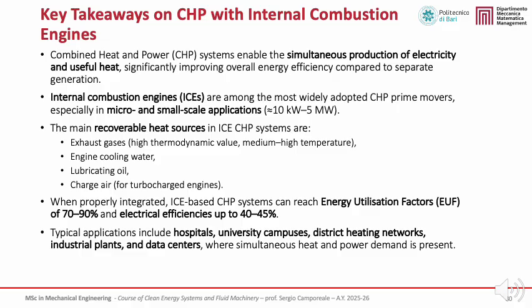The main recoverable heat sources include exhaust gases, which provide the highest temperature level, as well as the engine cooling circuits, lubricating oil, and charge air. When these heat sources are properly exploited, ICE-based CHP systems can achieve very high energy utilization factors, often exceeding 70%, making them ideal for applications with continuous and simultaneous heat and power demand.